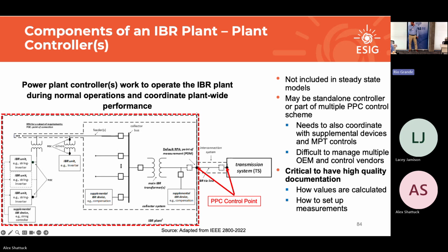You may also, in weird cases, have two independently operating plant controllers, which is what they all look like in the PSPD generic model world, because you can't model that in the PSPD or with a generic model. There's no main-secondary mapping, right? So this is one of those situations where it's really critical to have the EMT and do the modeling of the actual communication in the main and secondary hierarchy. But if you see two, it doesn't mean it's wrong.